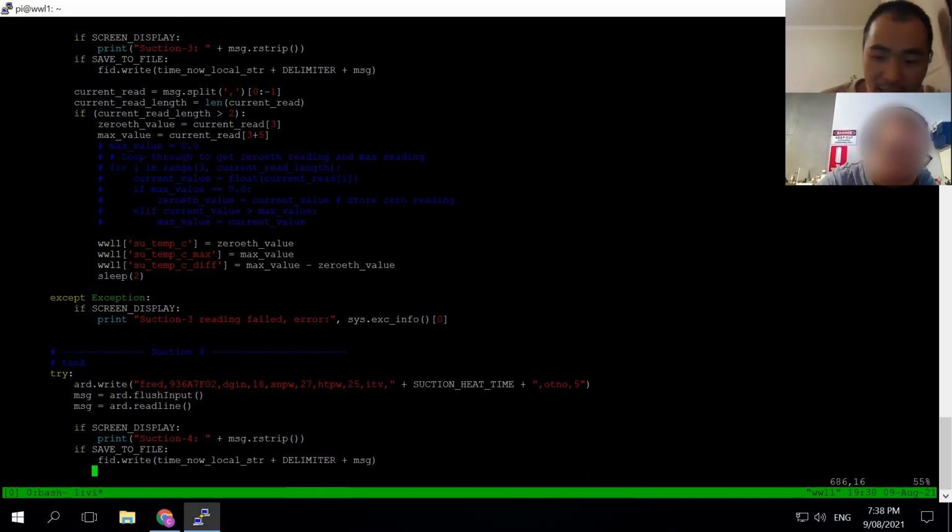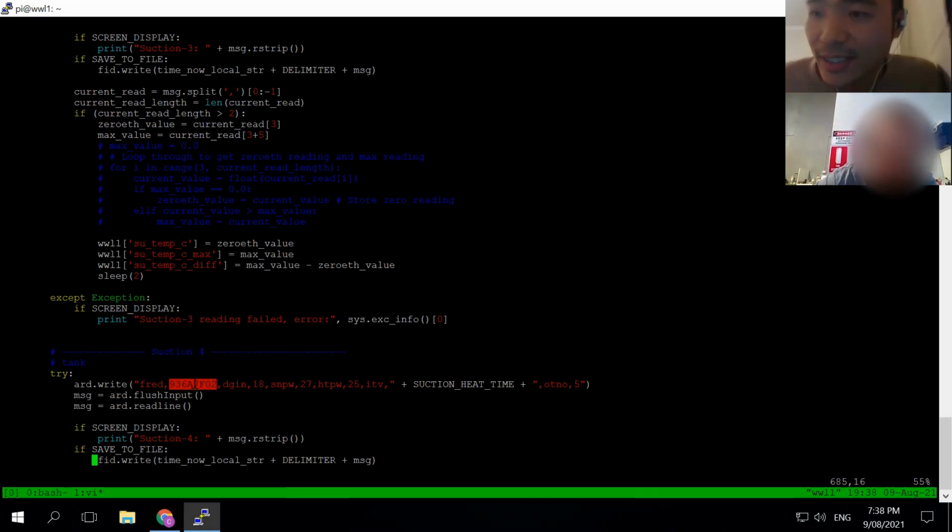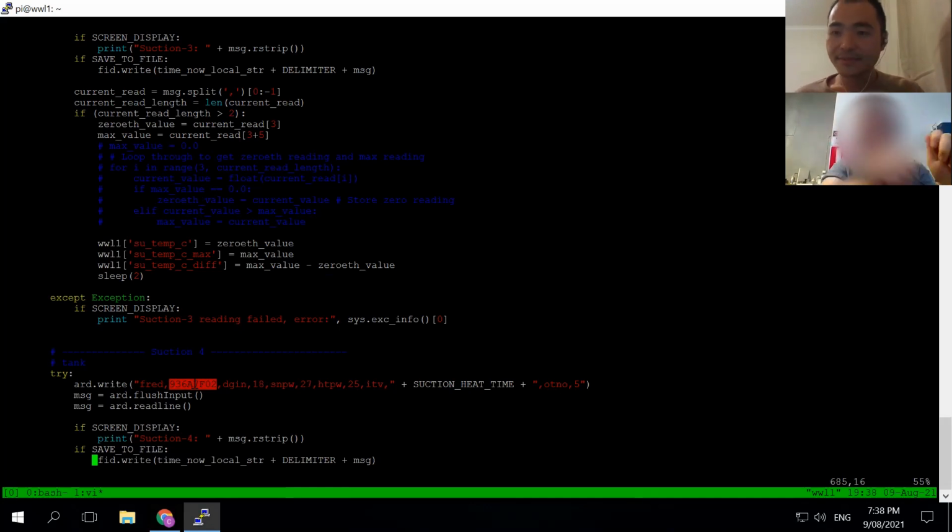And the thing that I need to change, in particular for the suction sensor, is that I need to associate the specific ID with that sensor. And again, if you always use that sensor with that ID, I don't have to do anything. That makes sense. But associating a sensor, I'd have to do it one by one, wouldn't I? I'd have to plug them in, do a test, and then go, that's that, and then plug a new one in. That way I can differentiate. Exactly. And then once it's done, it's completely finished.